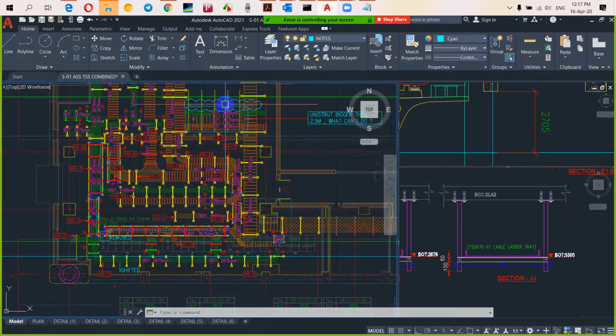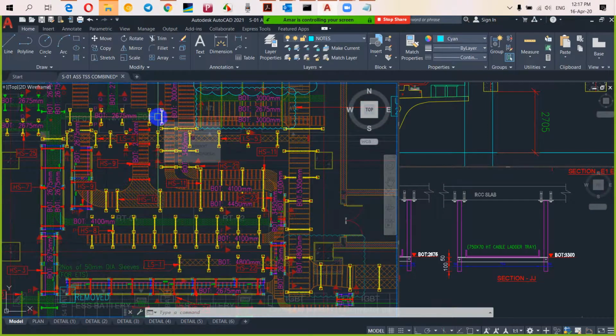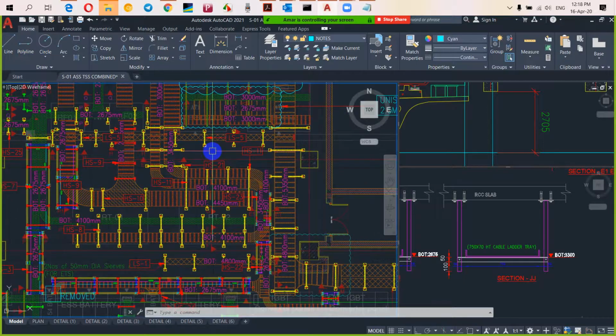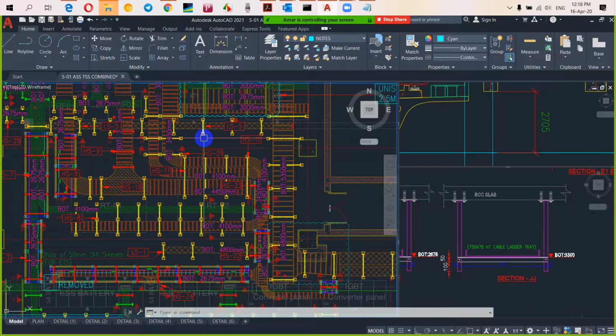Okay. So I will do some detailing and then see what can be done. Okay, then let me know if I can help. I'll let you know. If anything, I can adjust myself, or else I will update. But basically, 33 kV clubbed with the LT tray is not suggestible. Yeah, that's the reason I don't want to club it actually. Yes, the LT cable tray, let us club, no issue. But the 33 kV tray we cannot club.